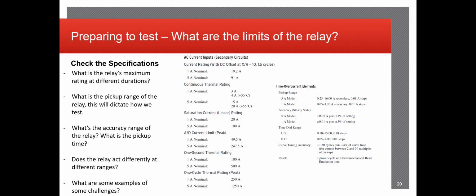Again, going over the limits, making sure you are aware of the maximum rating for different durations. This is especially prominent for the current ratings. Usually you won't exceed anything over 5 amps besides a fault scenario. So when you trigger a fault through your currents, you want to make sure you don't overload the relay or even the test set itself by exceeding the current limit.